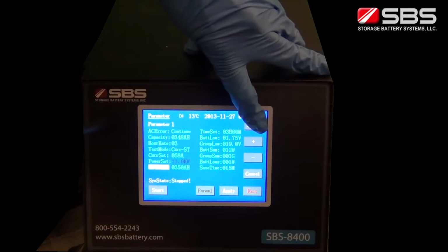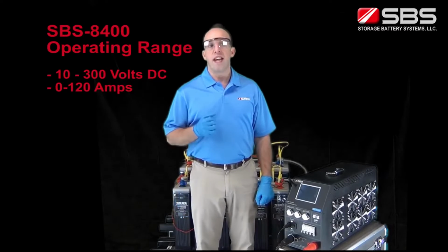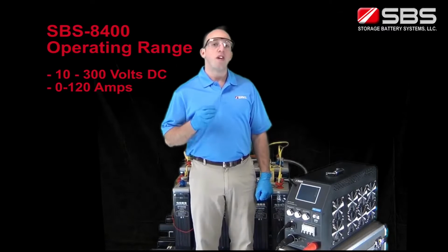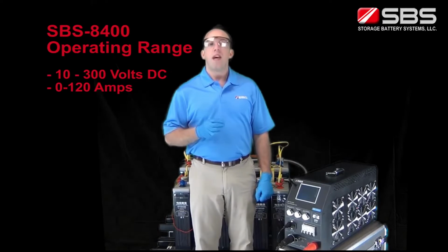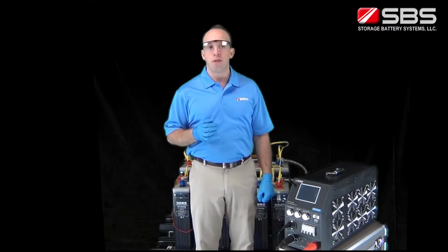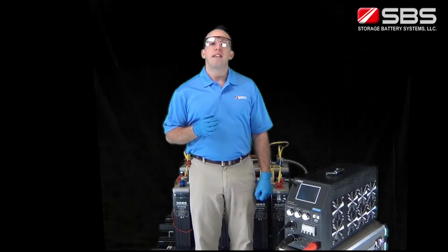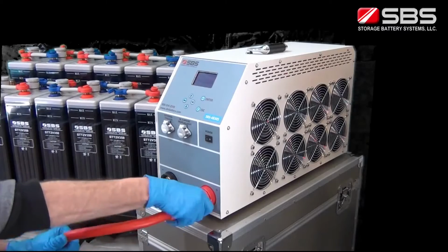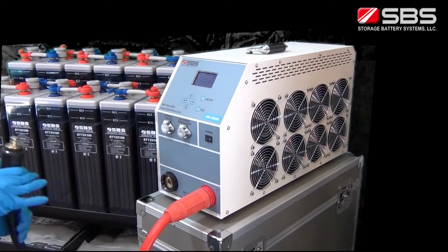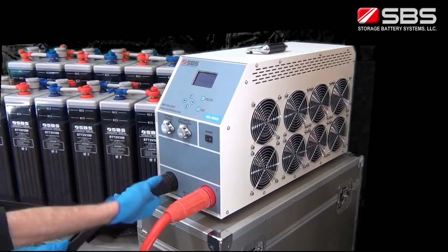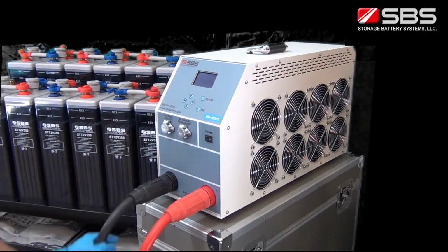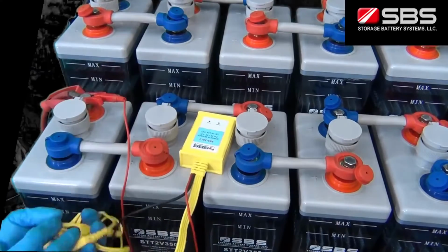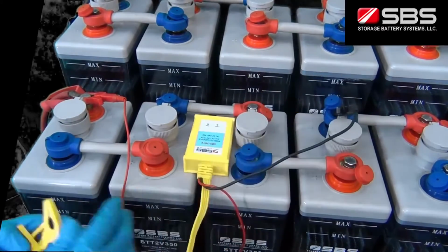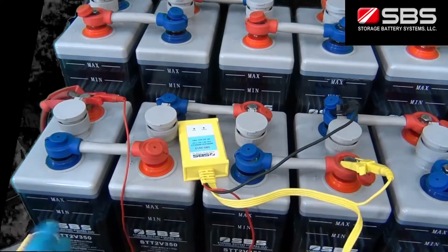The SBS-8400 has a much wider operating range, from 10 to 300 volts DC and 0 to 120 amps. Because the SBS-8400 is such a flexible unit, it can replace having to purchase multiple units for different voltages. The SBS-8400 can operate in parallel with our S-series of load banks. This means you can use the SBS-8400 as a master load and parallel other load banks in to increase the total discharge current capacity.